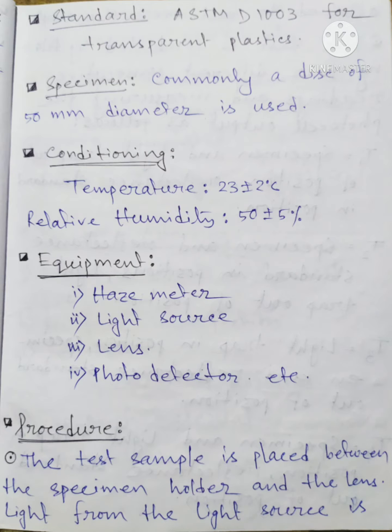The standard is ASTM D1003 for transparent plastics. A specimen commonly used is a disc of 50 mm diameter. Conditioning temperature is 23 plus or minus 2 degrees, relative humidity 50 plus or minus 5 percent. Equipment used includes a hazemeter with a light source, lens, and photodetector.